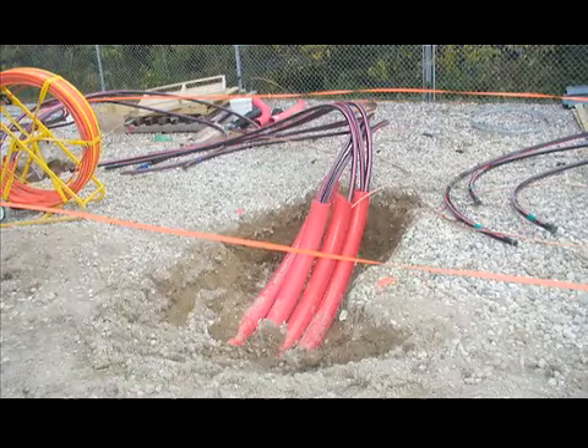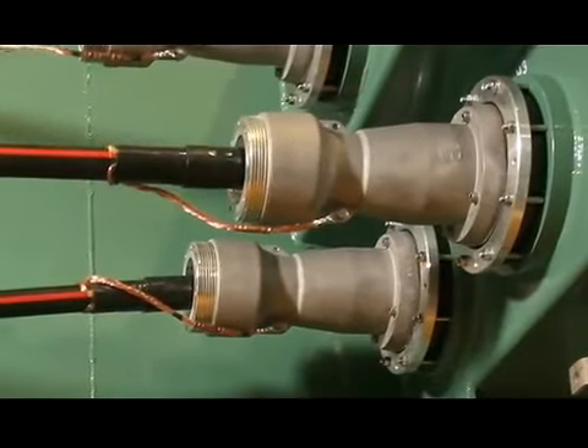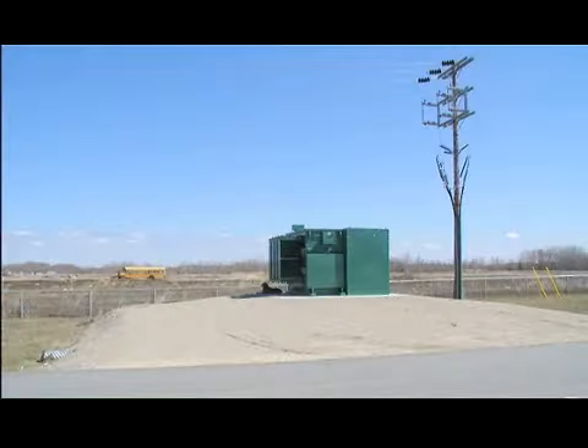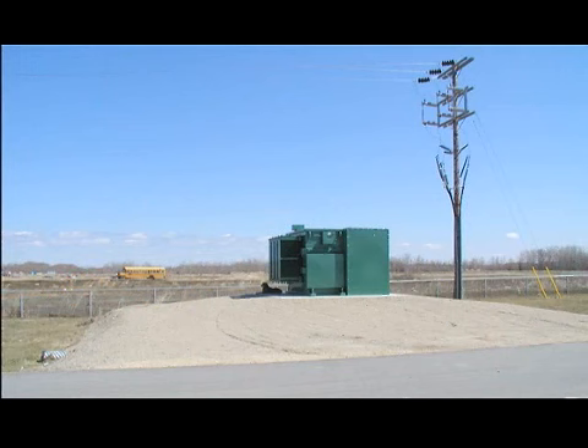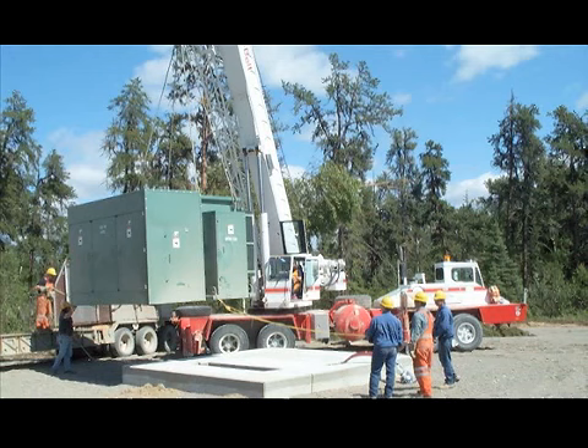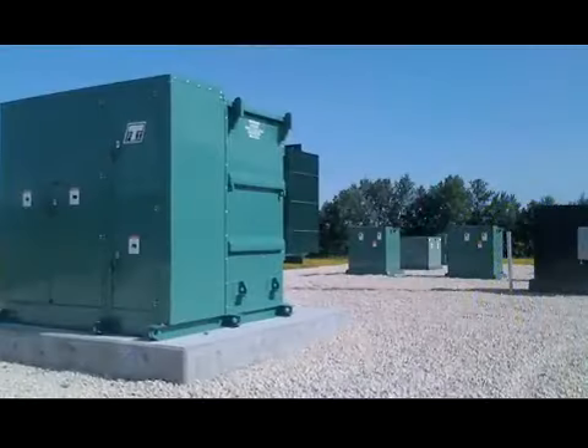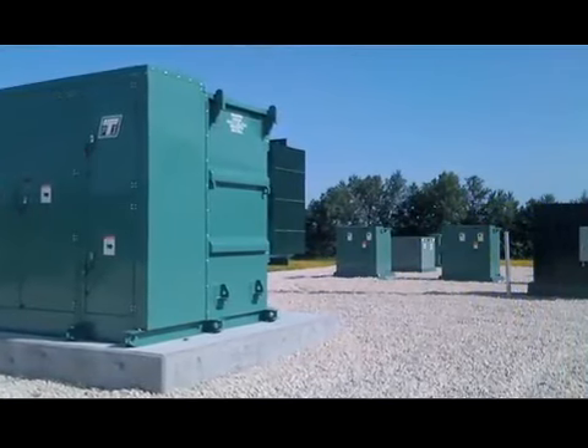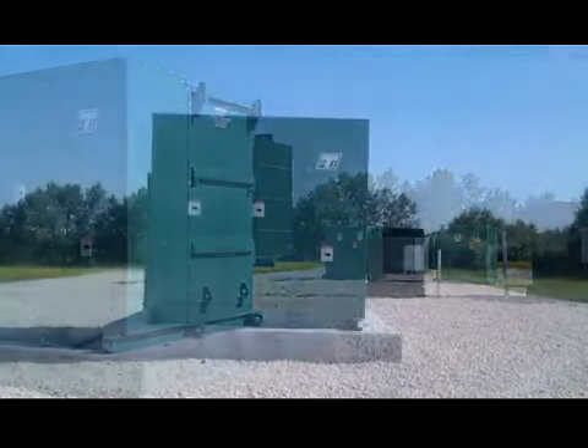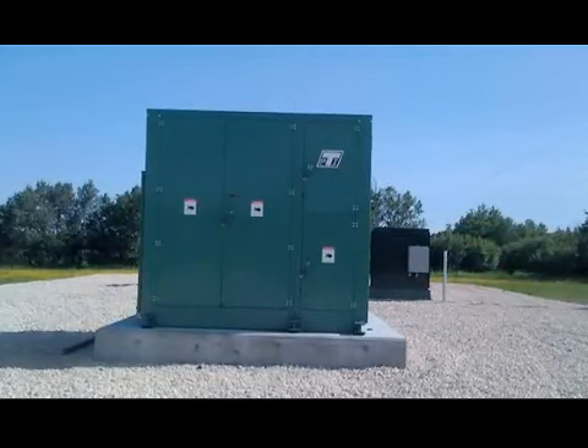Appropriate grounding designs exceeding IEEE 80 requirements ensure the safety of the public, and the nature of the Padmount design allows for 5 MVA to 10 MVA stations to fit onto a 100 by 100 foot lot. It's a smaller footprint than one of our large 115 kV stations or 66 kV stations where you would have a lot of oil-filled equipment, oil-filled breakers, larger transformers. This is a smaller idea, smaller footprint, more focused on a specific load or a specific area as opposed to a large blanket solution to a geographical area.